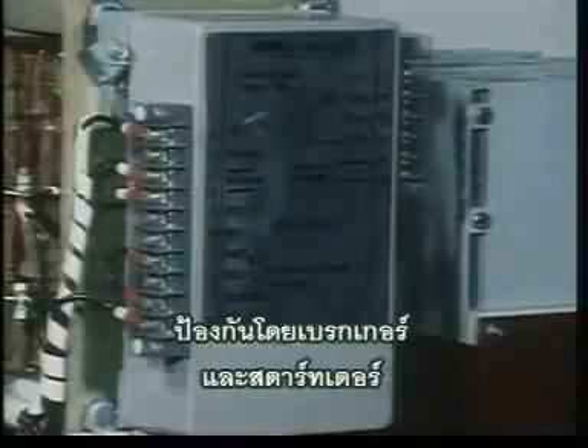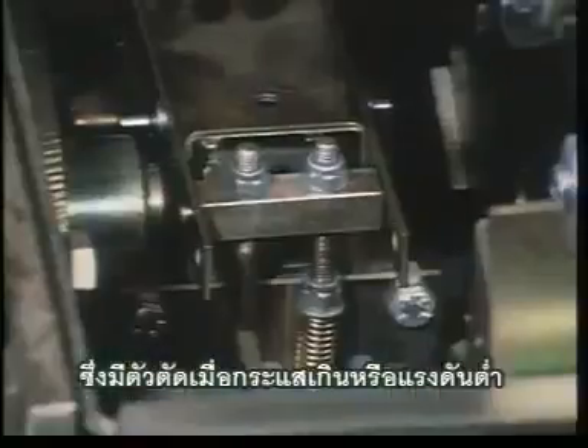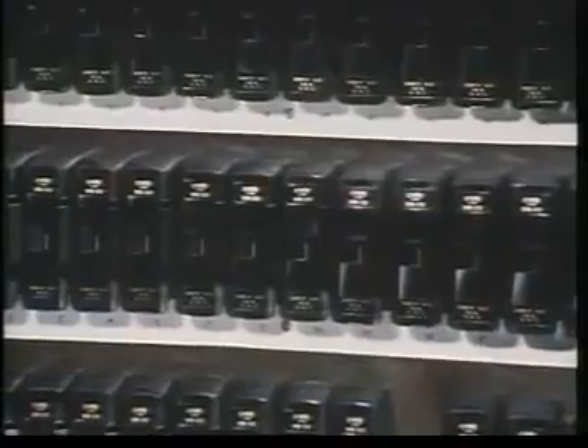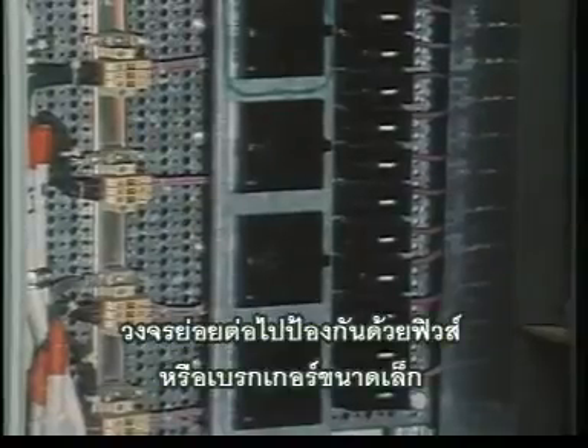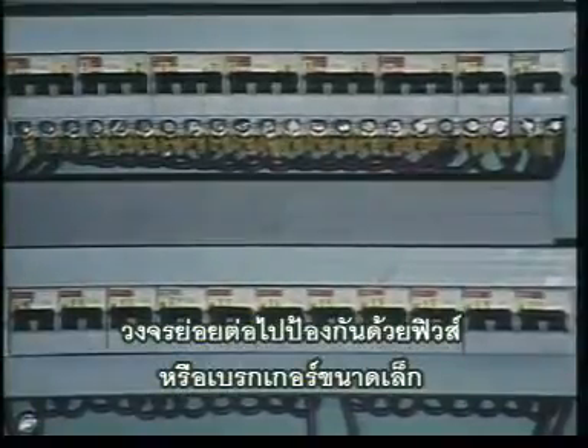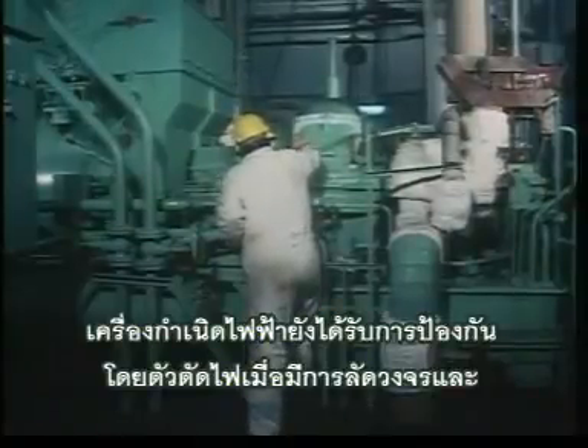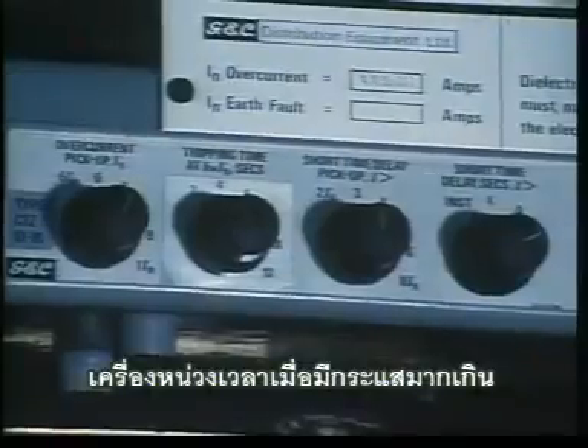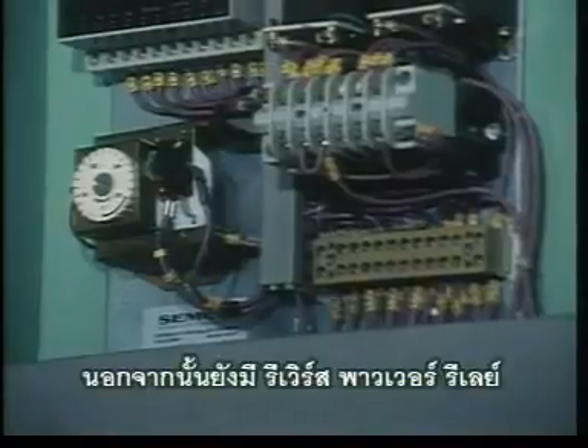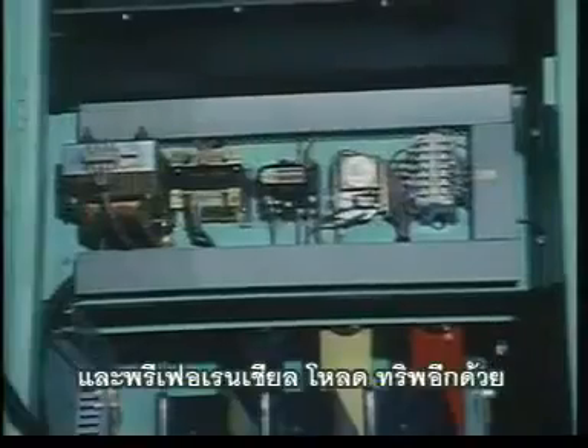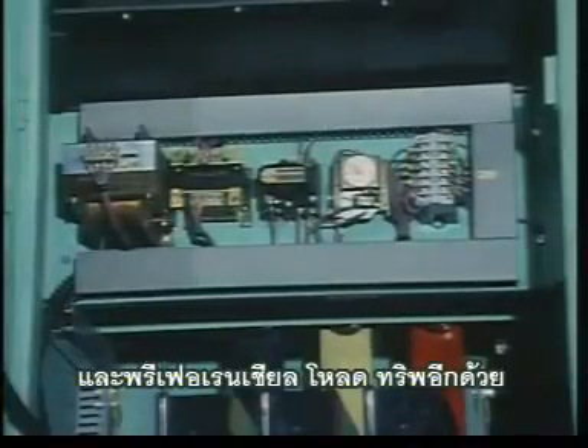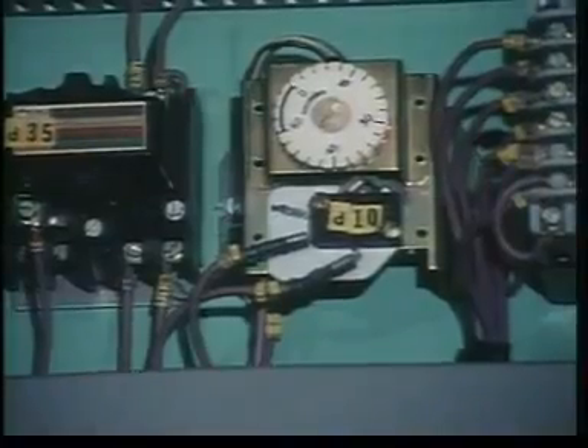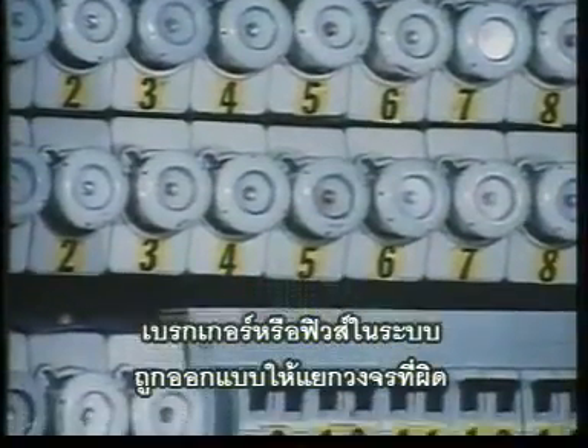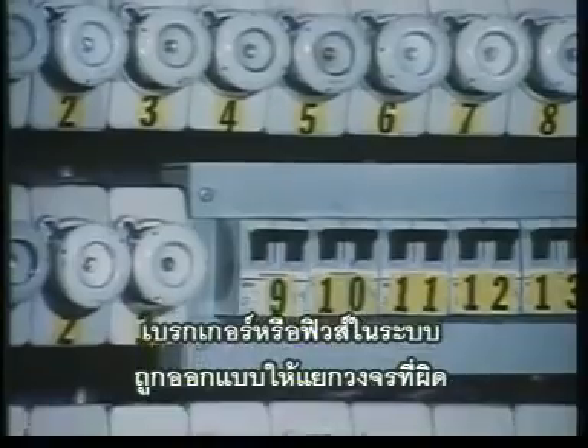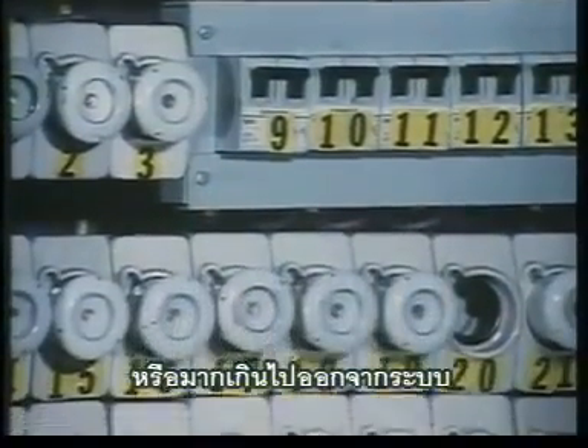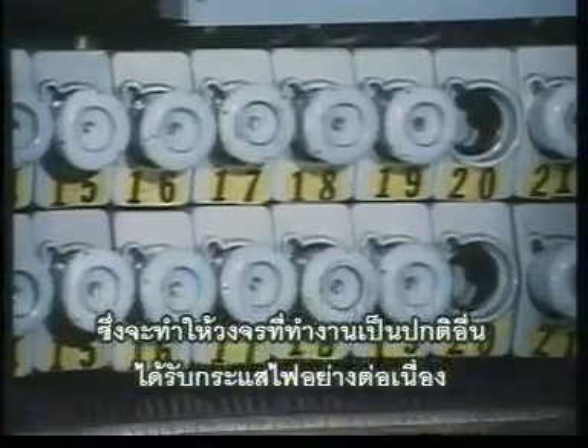Protection is provided by circuit breakers and starters with overcurrent and under voltage trips. Each branch circuit is further protected by fuses or miniature breakers. The alternators are further protected by instantaneous short circuit and time-delayed overcurrent trips. Reverse power relays and preferential load trips are also provided. Each circuit breaker or fuse in the system is designed to isolate a faulty or overloaded circuit from the system, which ensures the continuity of supply to all other healthy circuits.